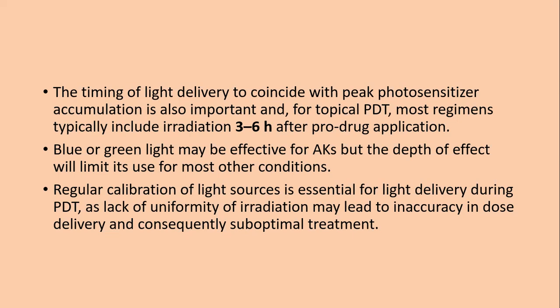Light irradiation should occur at the time when the prodrug has been converted into the photosensitizer, which is verified using Wood's light before starting treatment. Blue-green light sources may be effective for actinic keratosis, but the depth of effect is limited, as blue light cannot penetrate beyond 1–2 mm. Regular calibration of the light source is essential to ensure uniform irradiation and accurate dose delivery.